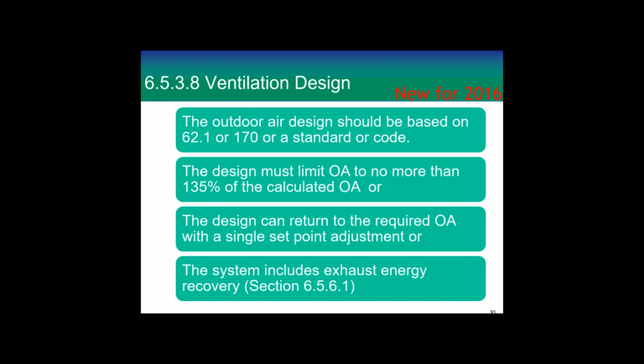Ventilation design. The outdoor air design should be based on ASHRAE 62 or 170 or a standard code. 170 is the hospital code. The design must limit outside air to no more than 135% of the calculated outside air. Now, or the design which can return, or you can set it up so that the controls can return to the required outside air with a single set point adjustment, or the system includes exhaust energy recovery.